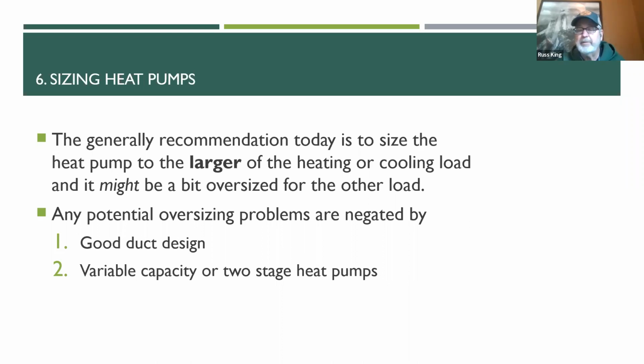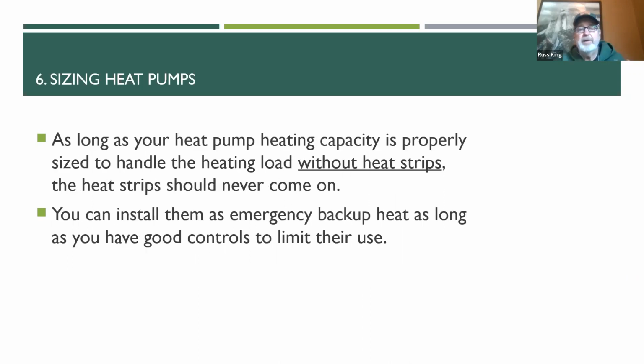We call that variable capacity or two-stage heat pumps. And what those do is instead of being one speed and being oversized part of the time, they're able to throttle down and reduce their capacity so that they're not oversized on the milder days, okay? So as long as your heat pump heating capacity is properly sized to handle the heating load without heat strips, the heat strips should never come on. You shouldn't need them, all right?